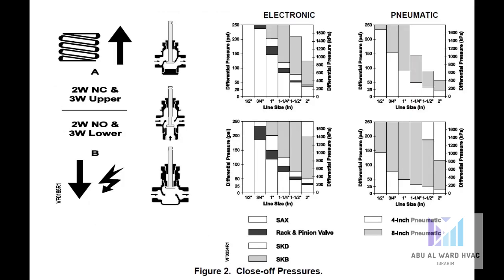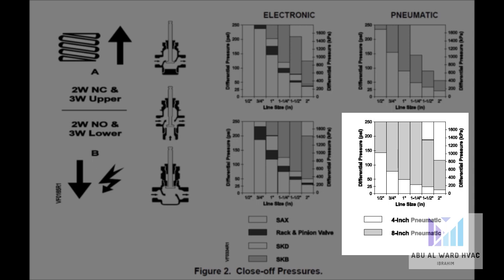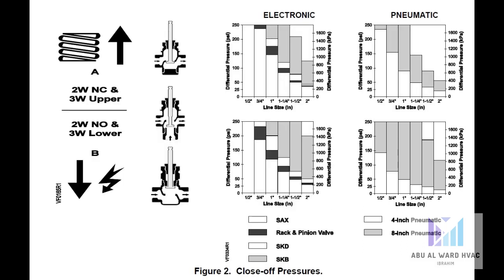Next, we go to the actuator selection. According to the graph for pneumatic actuators for normally open valves, we locate the one-inch valve in the lower right side of the figure. The gray shaded bar represents an 8-inch pneumatic actuator. In this case, the 8-inch pneumatic actuator has sufficient force to provide tight close-off against more than 50 PSI differential pressure.